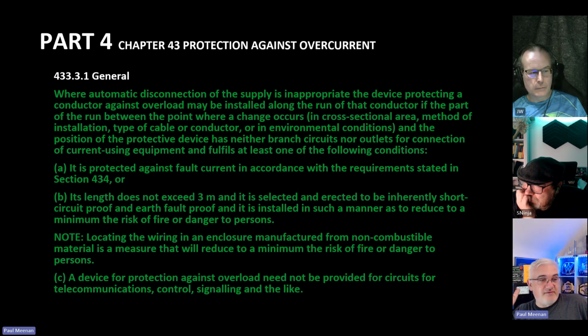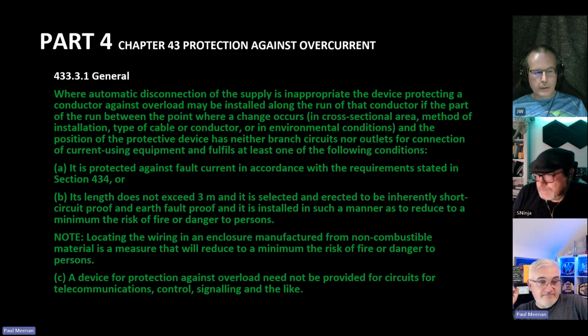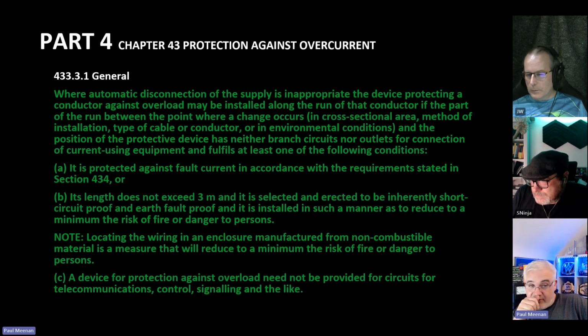Method of installation, type of cable or conductor, or environmental conditions, and the position of the protective device has neither branch circuits nor outlets for connection of current using equipment and fulfills at least one of the following conditions. It is protected against fault current in accordance with the requirements stated in 434. Its length does not exceed 3 meters, and it's selected and erected to be inherently short circuit proof and earth fault proof, and it is installed in such a manner as to reduce to a minimum the risk of fire and danger to persons. That's quite a good note, that.